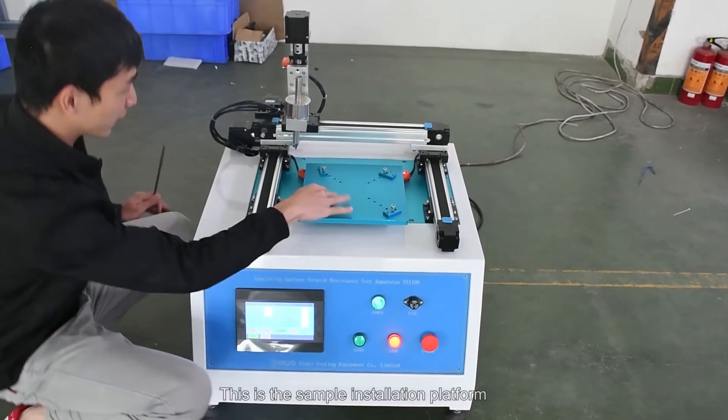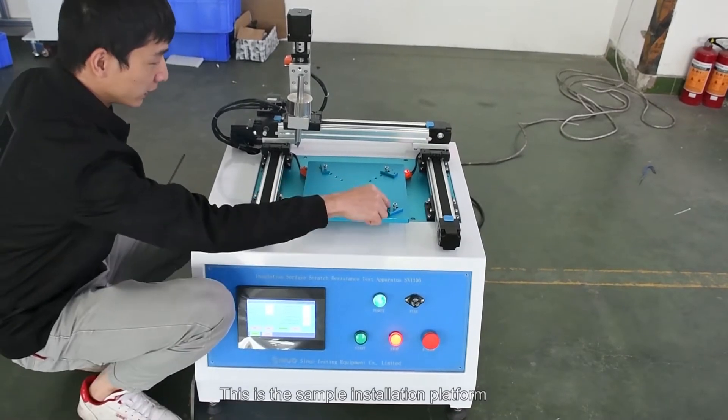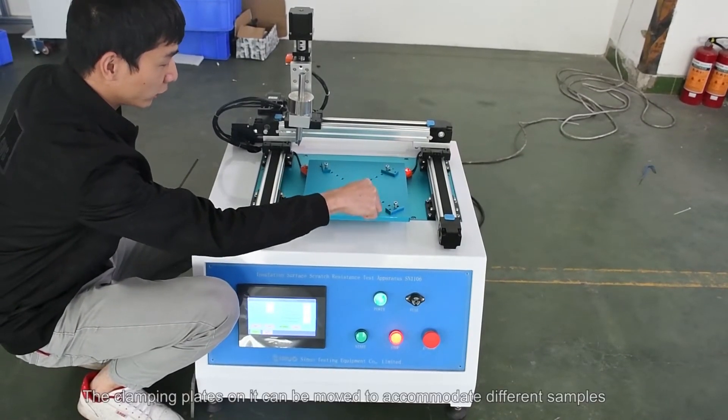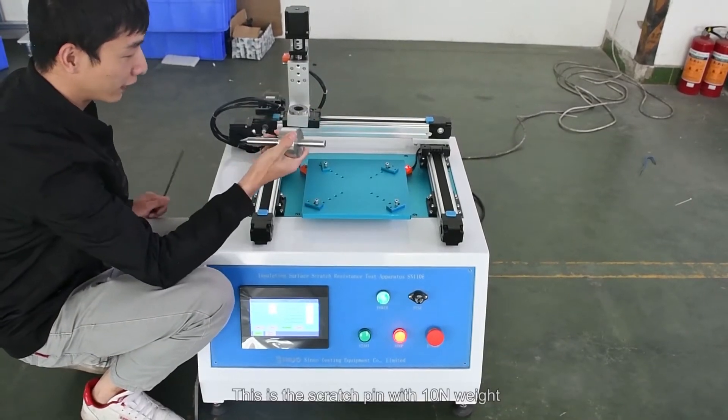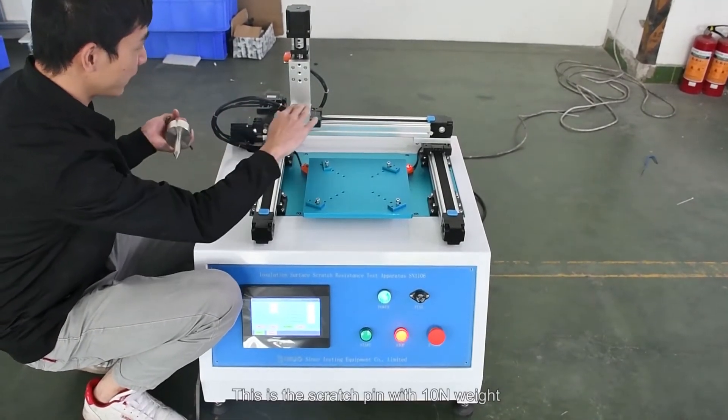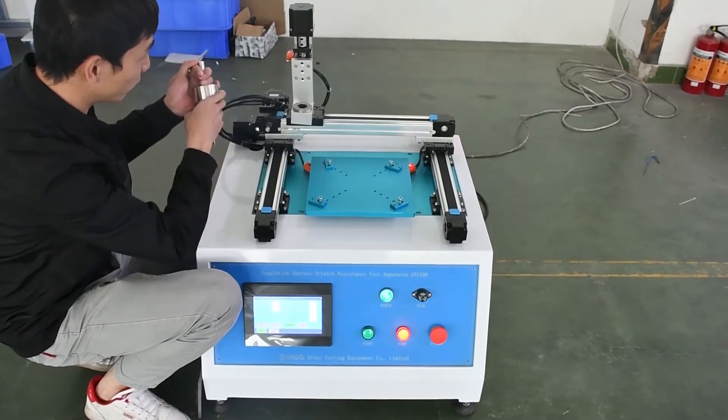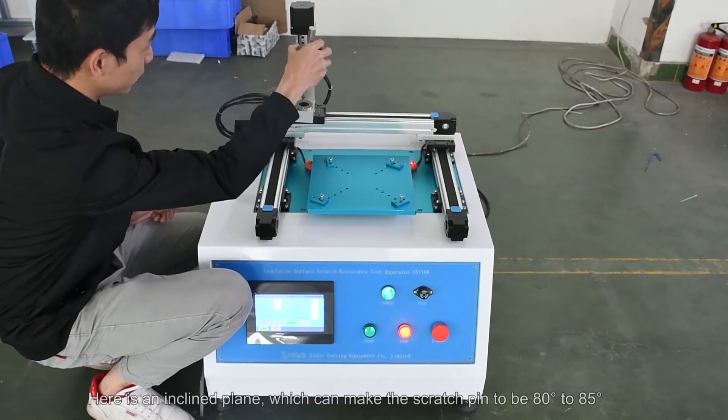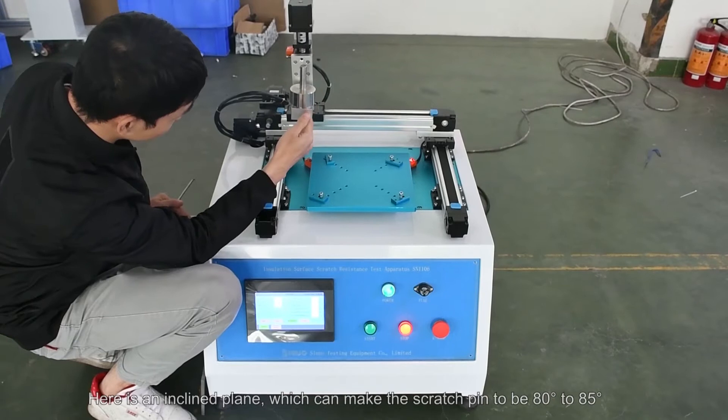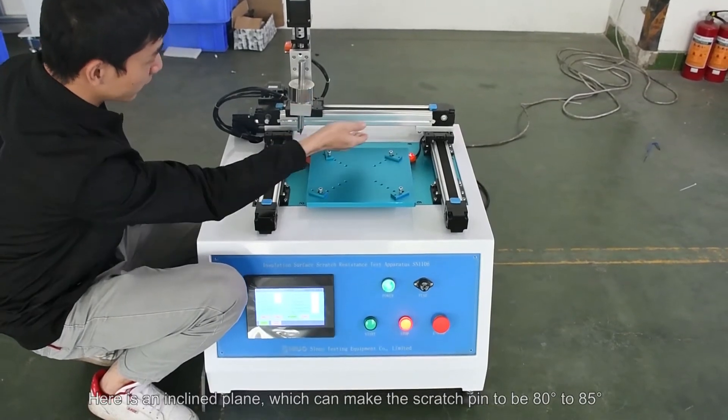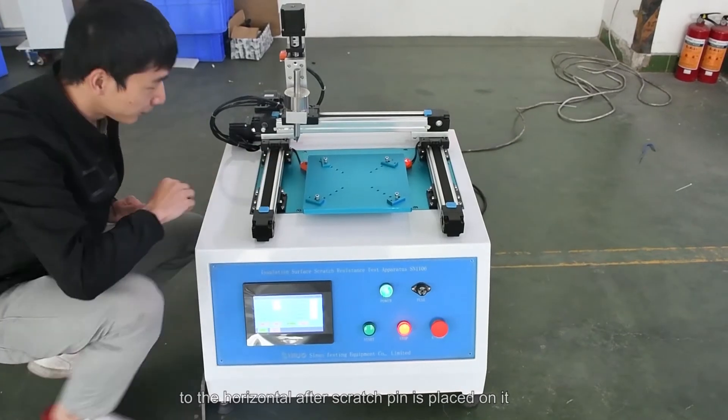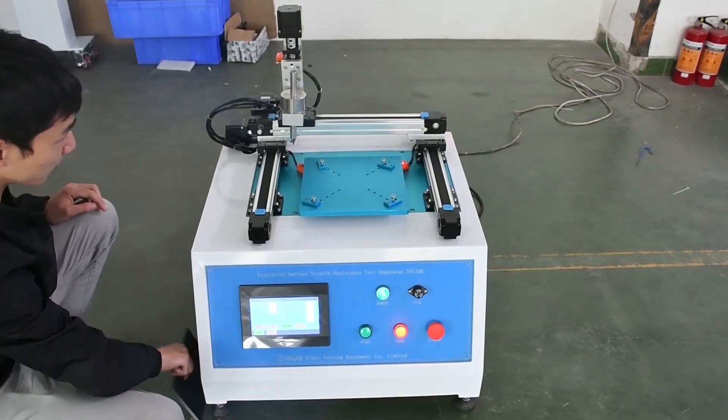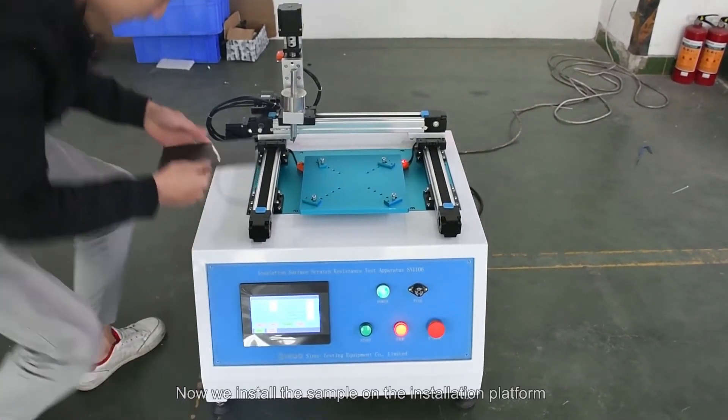This is the sample installation platform. The clamping plates on it can be moved to accommodate different samples. This is the scratch pin with 10N weight. Here is an inclined plane which can make the scratch pin to be 80 degrees to 85 degrees to the horizontal after scratch pin is placed on it.